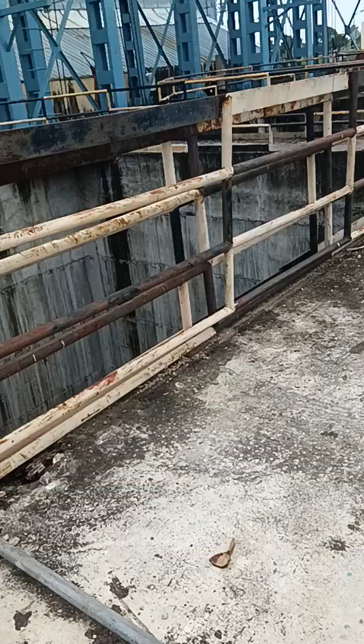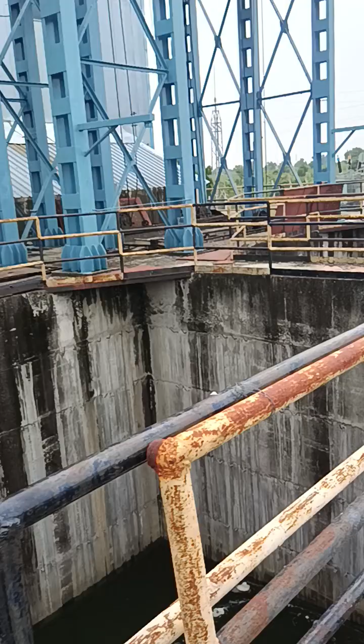We basically have three units of 4.5 megawatts each. Those are the intake service gates, and we also have one intake stopper gate. These gates are used to stop the water inflow inside the turbine whenever required, like during shutdown maintenance, for example hub body maintenance of the turbines, when we are not supposed to have water inside the turbine. For that purpose we use those three service gates.